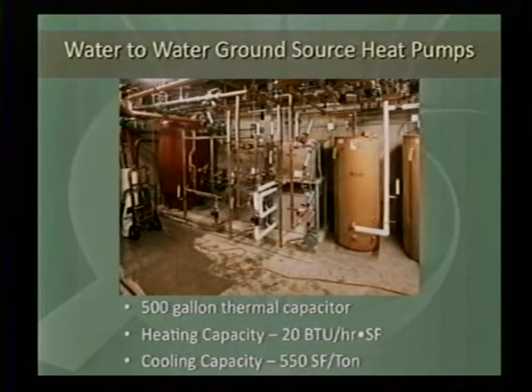What happens is when that tank drops down to 105, the heat pumps go on, and basically they're working to heat up 500 gallons of water. So they can operate at a very efficient duty cycle, refill the energy in the tank, and then you dribble the energy out to the building as you need it. It goes out of the tank and then you bring it back up again.